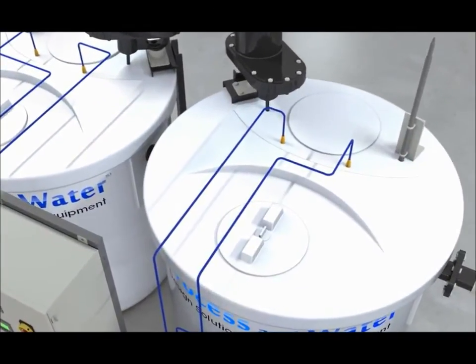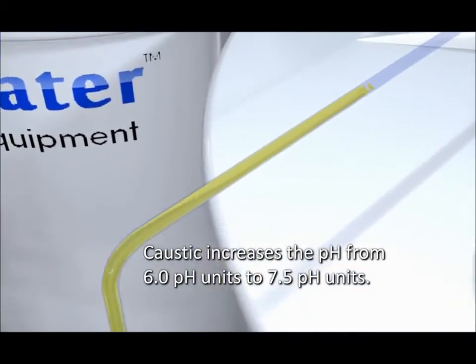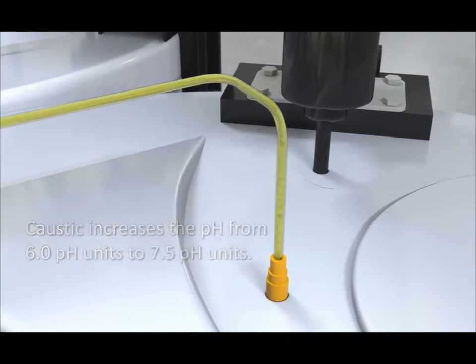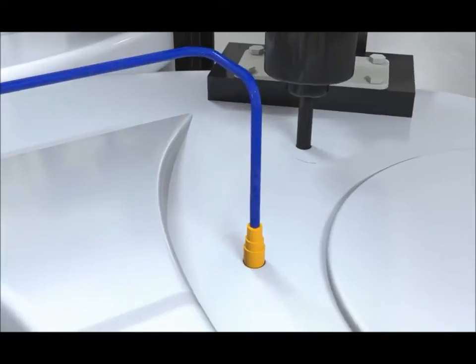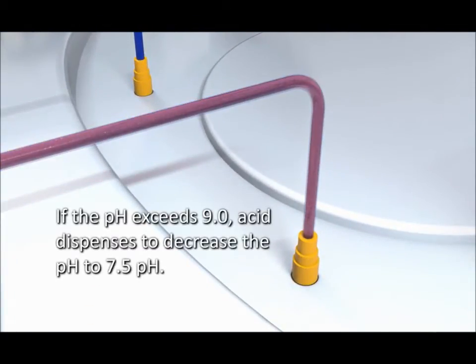The second caustic metering pump feeds the chemistry once again to increase the pH from the 6.0 pH units to 7.5 pH, and if the pH should increase more than desired to over 9.0 pH units, then the acid pump feeding this tank will feed acid to decrease the pH to 7.5 pH units.